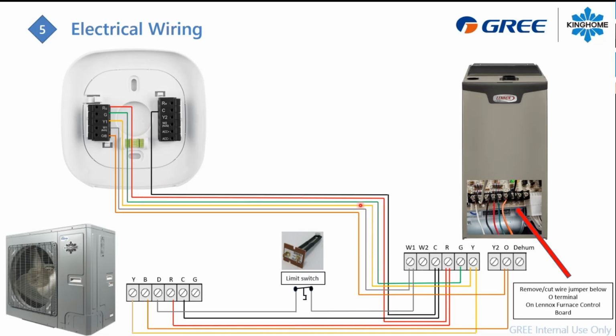And all those wires will be connected to the furnace board. In that example, this is a Lennox 2-stage furnace. So you will have your W1, W2, C, R, G, Y, and an O terminal right here. O and B terminals are both for the reversing valve, but in that case, you need to cut the wire jumper just below that O terminal when it's a Lennox 2-stage furnace.